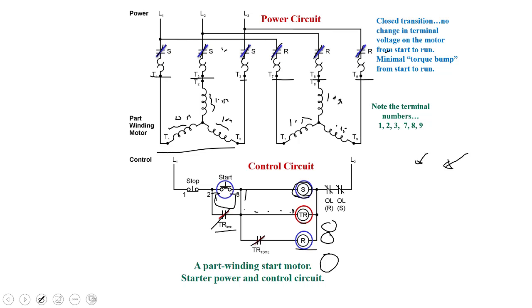So we also call this a closed transition starter. What's a closed transition starter? When we're transitioning from start to run, some of the starters that we're going to look at remove the voltage completely from the motor before they reapply the voltage at full voltage. So they take away the reduced voltage for a moment in time, then the motor has no voltage across it. That creates something called a torque bump and a little bit of a spike in current at that point when we're transitioning from start to run. This one is a closed transition, meaning that the motor never goes without a source of energy or supply voltage while we're transitioning from start to run.